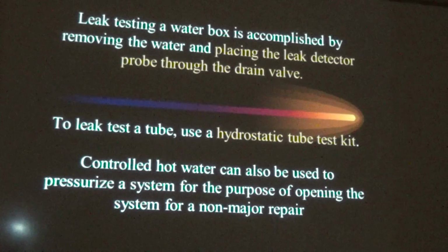Leak testing a water box is accomplished by removing the water and placing a leak detector probe through the drain valve. That one's definitely on the test, I just saw it the other day. To leak test a tube, use a hydrostatic tube test kit. I also mentioned that this sheet here is a little bit shorter, but this one gets to the point pretty good.